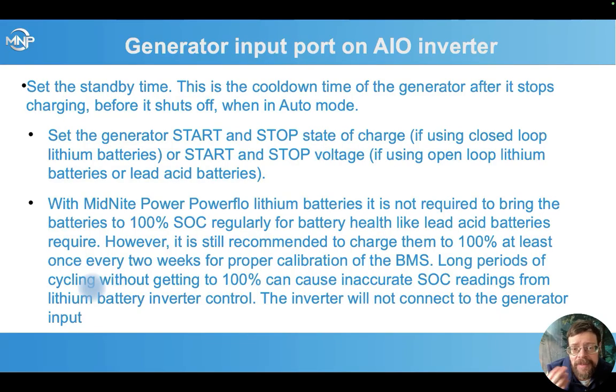You set the standby time, which is the cool down time of the generator after it stops charging before it shuts off. This only applies to the auto mode. In manual mode, you're manually turning the generator on and off. And you can set the start and stop state of charge.